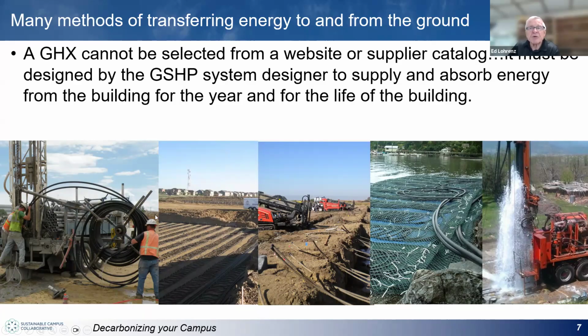If you've got a lot of space, we can excavate a large hole in the ground, put a bunch of pipe in it, fill it back in, and take the heat from that mass of dirt. This might only be 6, 7, 8, or 9 feet deep. We've done a lot of schools this way, where there's a lot of property.